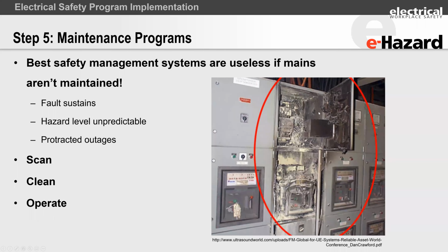Step 5 is going to be your maintenance program. Folks, you can have the best safety management systems, the most beautiful arc flash labels, the newest, greatest piece of equipment. But if you have not maintained it, and if that main circuit breaker cannot trip and clear the arc flash energy or protect the worker against electrical shock, all of those safety management systems are going to fall on their face. Because of that, maintenance needs to take a forefront in electrical safety.